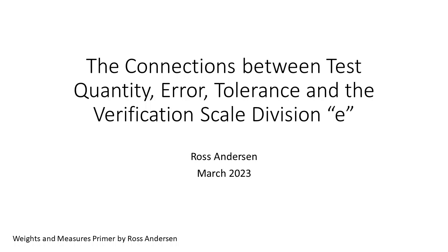The scale's code must be clear. Is it referring to E as in classification and E as the actual weight on the verification scale in testing? Or is it referring to D and the operation of the instrument scale? The Scales Code translation adopted back in 1984 blurred the distinction in some important cases and completely reversed the meaning in others, most notably expressing test loads and tolerances in Table 6 in D instead of E. The task group is making recommendations to resolve these translation errors and ensure the correct meanings are conveyed.